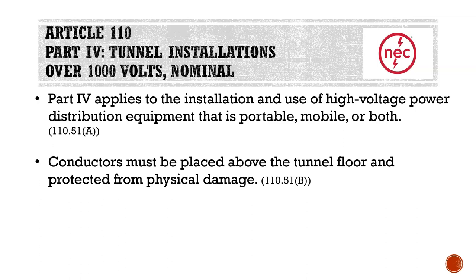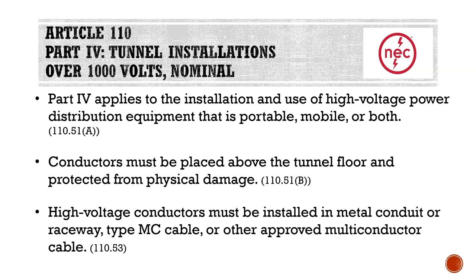Conductors must be placed above the tunnel floor and protected from physical damage. Specifically for installations in tunnels, we can't lay the conductors directly on the floor — they have to be elevated or suspended above the floor and protected from physical damage by some means. High voltage conductors — over 1,000 volts — must be installed in metal conduit or raceway, must be type MC cable, or other approved multi-conductor cable.